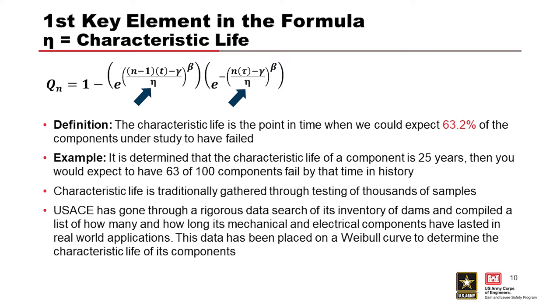Characteristic life is traditionally gathered through testing of thousands of samples. We have gone through a data search of the inventory of dams, both flood control and navigation dams, and compiled a list of how many and how long its mechanical and electrical components have lasted in real-world applications. This data has been placed on a Weibull curve to determine the characteristic life of its components.